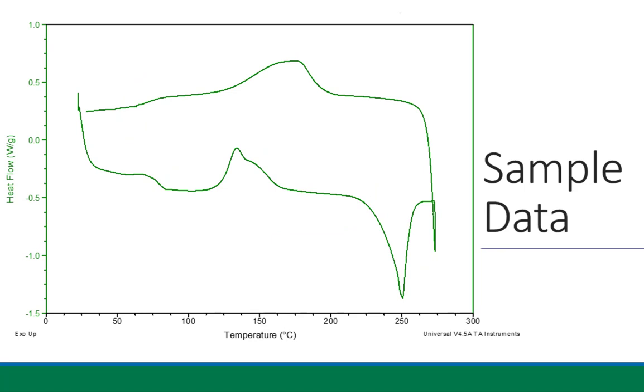Here we have an example data set. A typical DSC plot has heat flow on the y-axis, normalized for the mass of the sample. We always weigh samples before putting them in pans and input the mass into the software so it normalizes the y-axis. This is important because if two runs have different sample masses, the signal intensity will differ — by normalizing to mass you can compare runs without the mass effect. The x-axis shows temperature in degrees Celsius, though time can also be used.